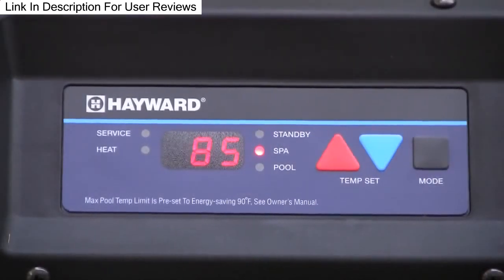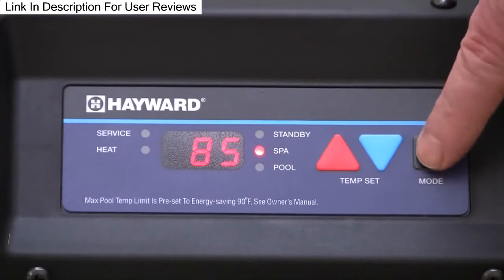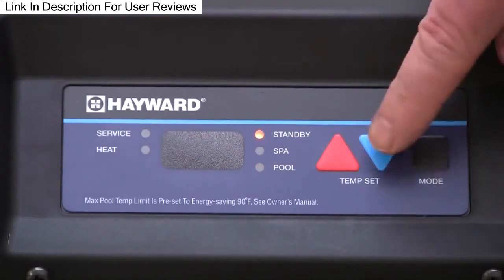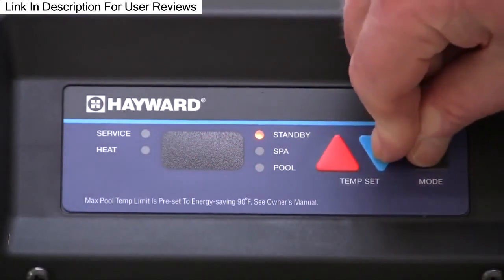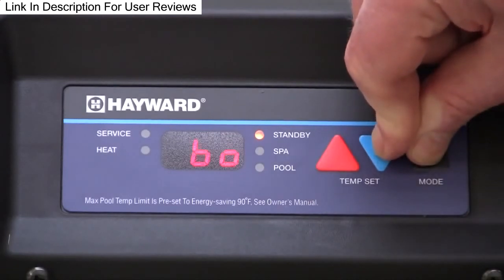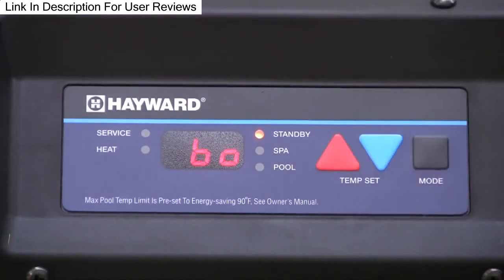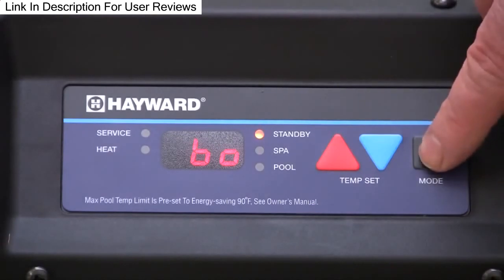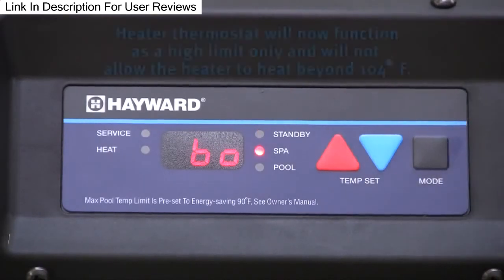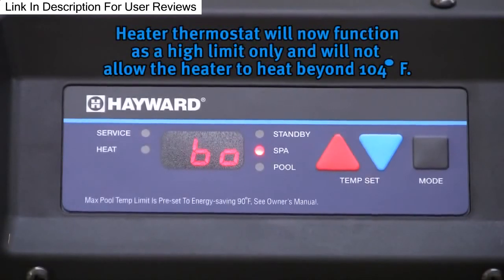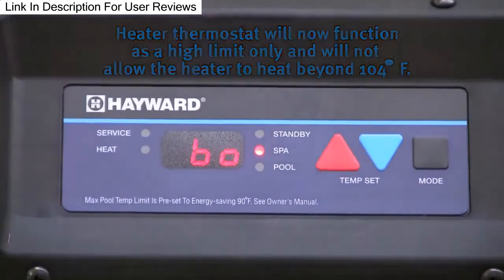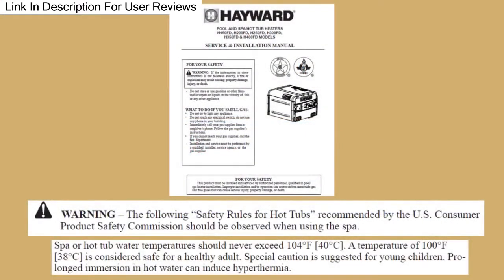Let's now talk about setting the control for operation with a remote controller such as Hayward's ProLogic. Using the mode button, place the heater in standby. Simultaneously press and hold the mode and down arrow for approximately 3 seconds. A BO will be displayed on the screen. Now the heater must be placed in either the pool or spa mode for remote control. The heater thermostat will now function as a high limit only and will not allow the heater to heat beyond 104 degrees Fahrenheit. Please refer to the Universal H Series manual for information about temperature setting limits.